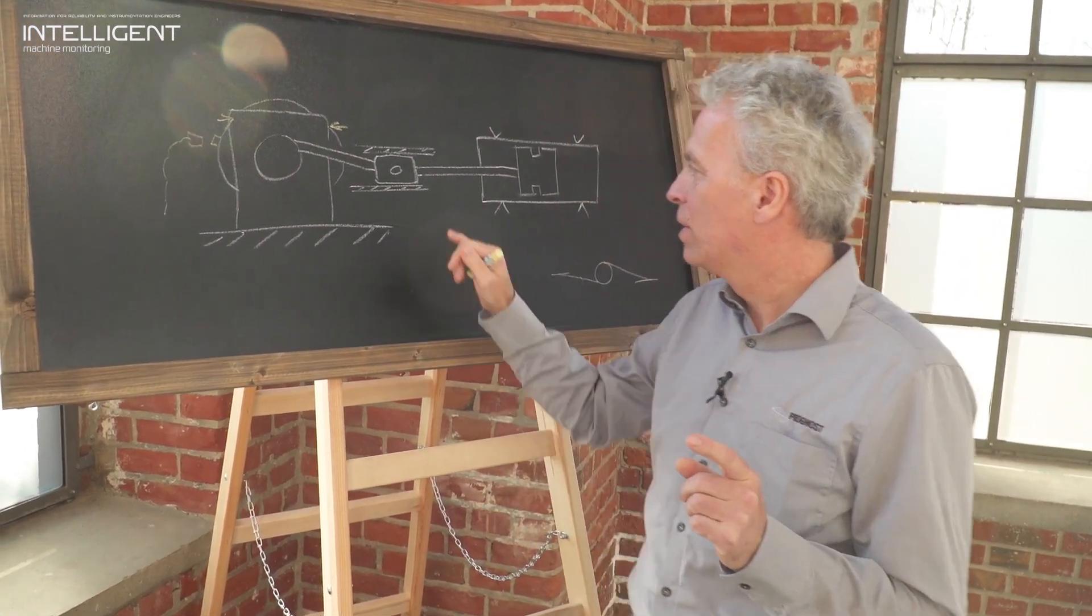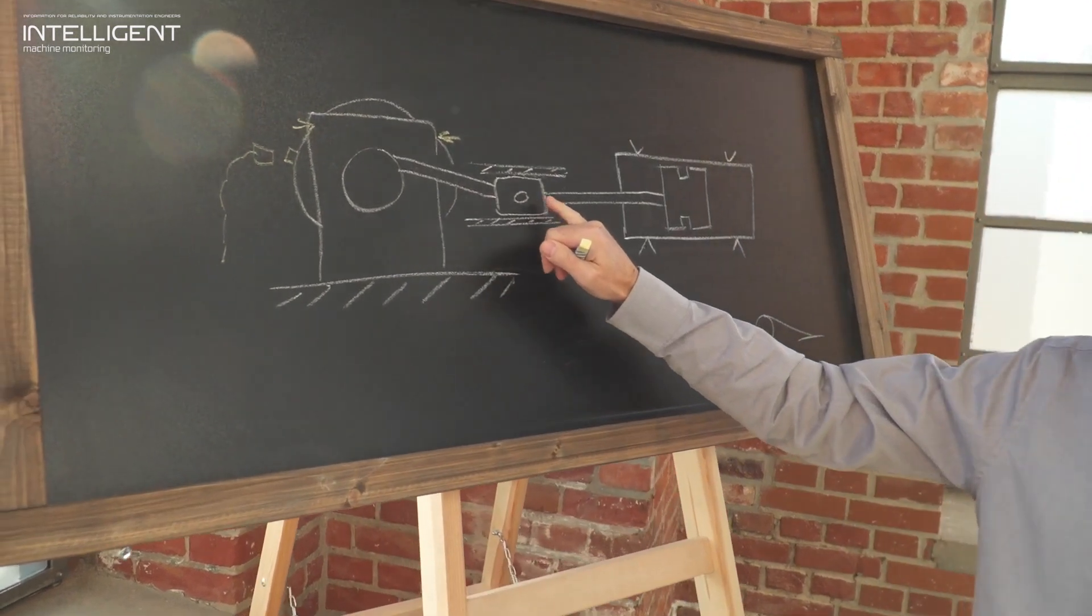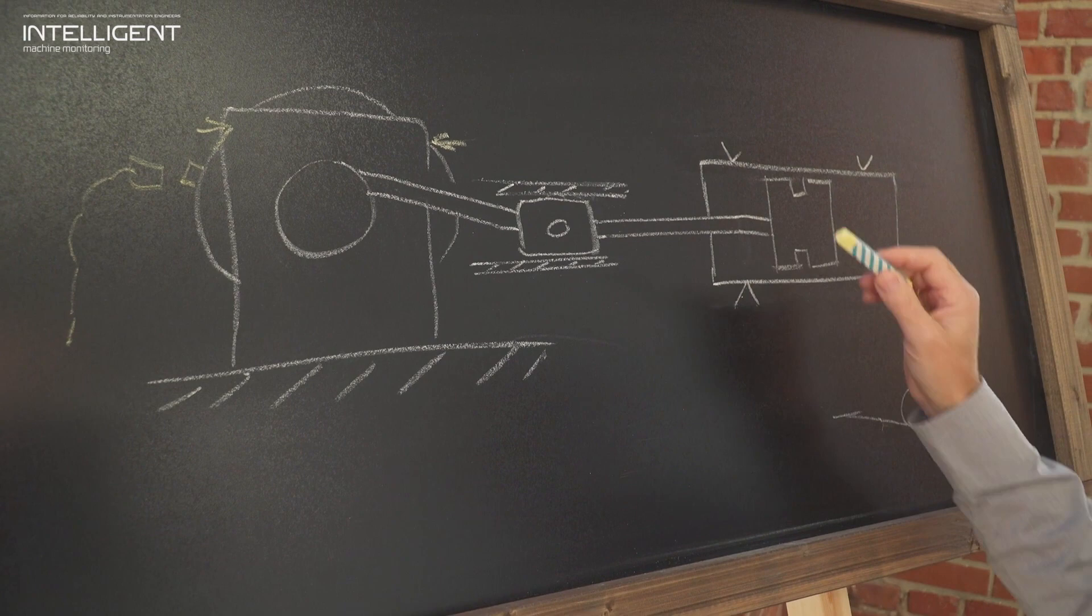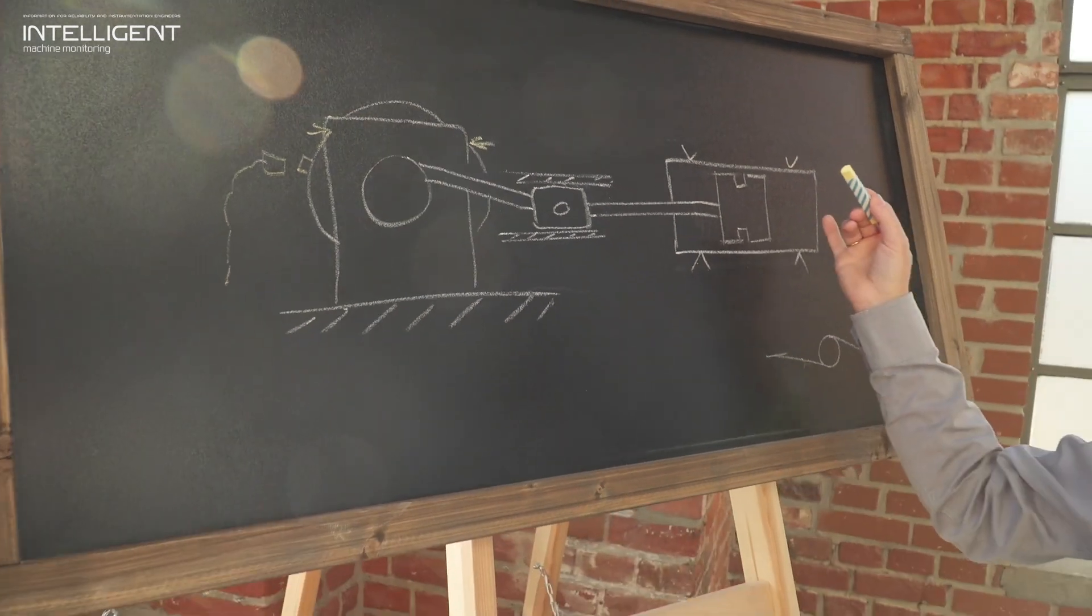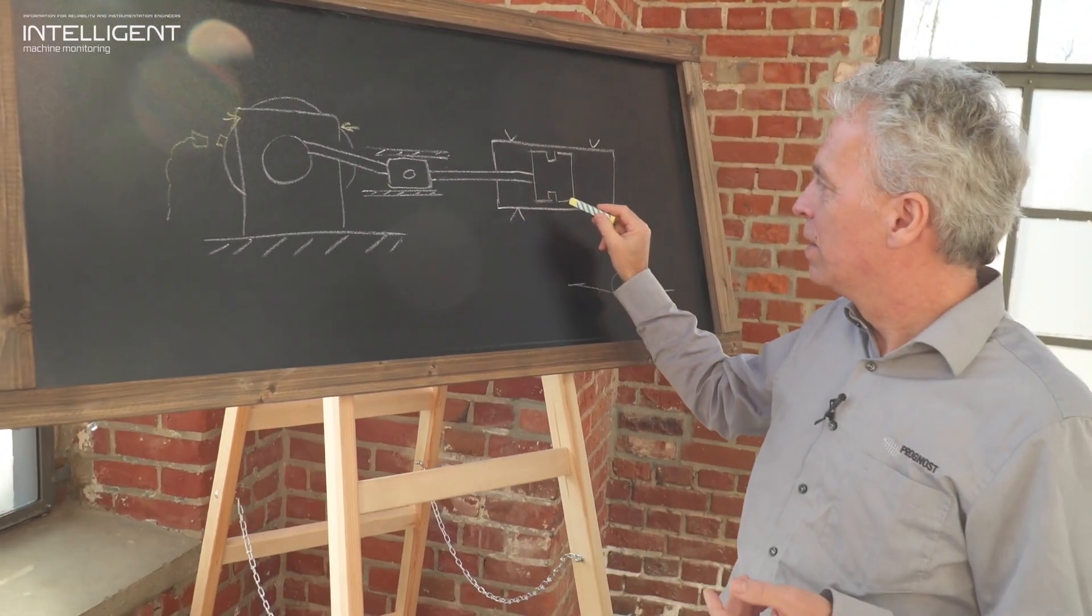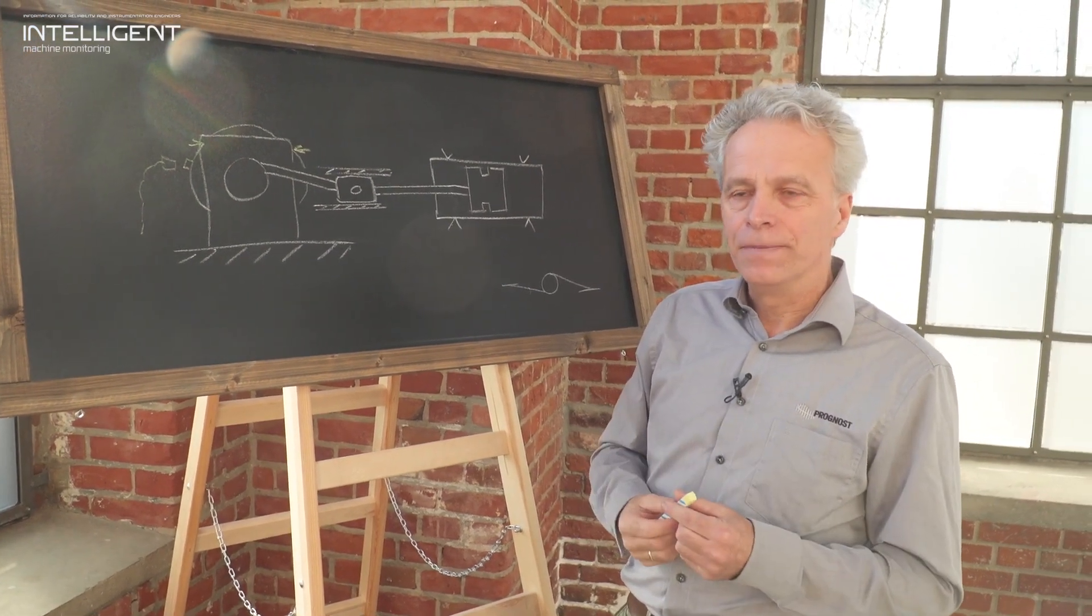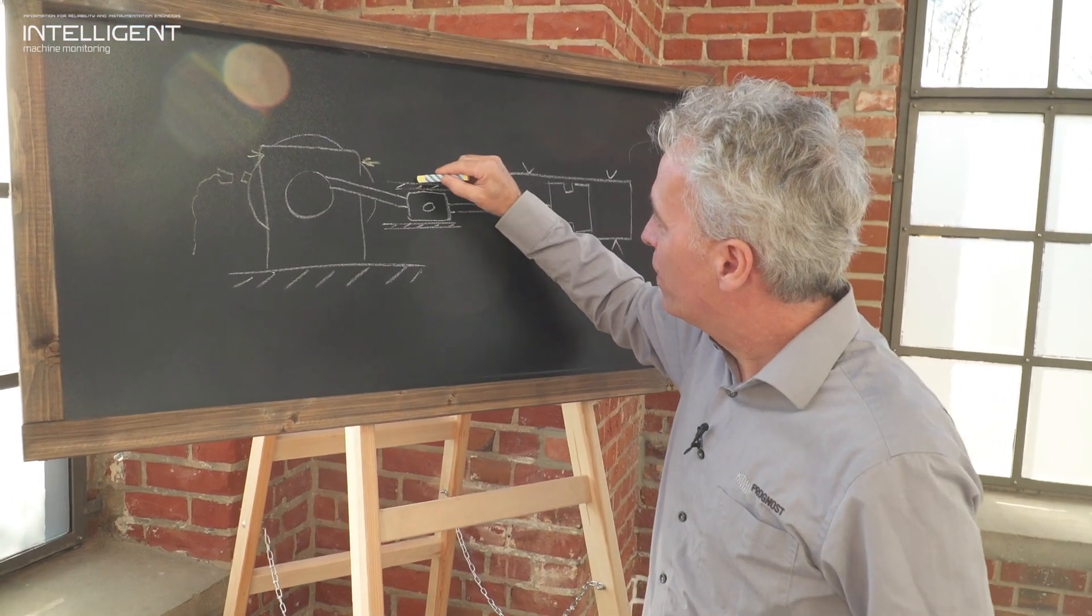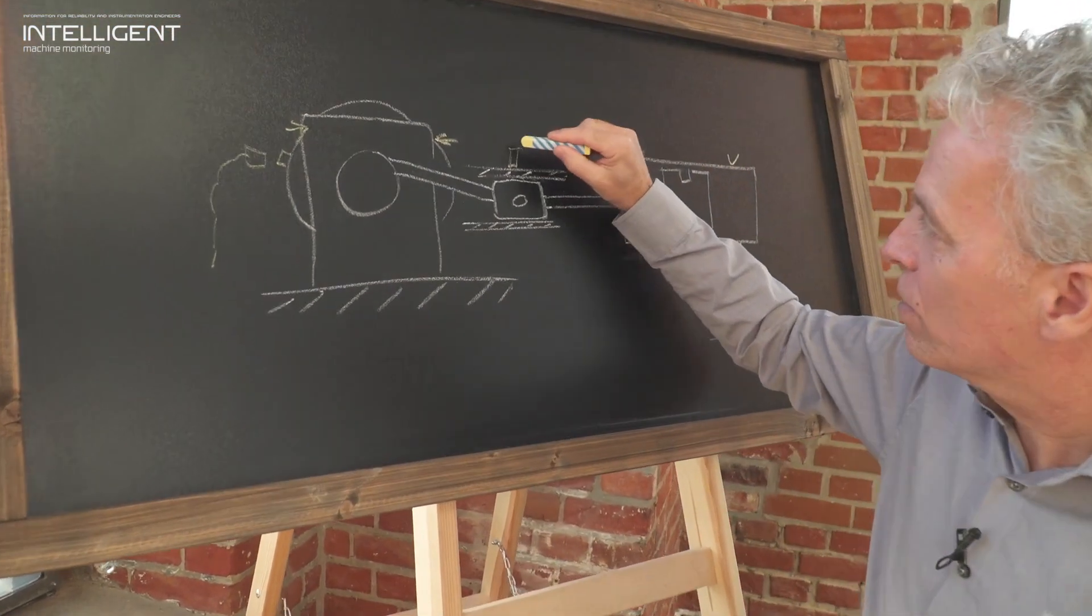In case it moves like this and bangs to the upper or to the lower crosshead guide, this indicates for example loose mechanical connections between the crosshead and the piston rod, or the piston rod and the piston. It might indicate liquid slugs, broken rider rings, or any mechanical disintegrity.